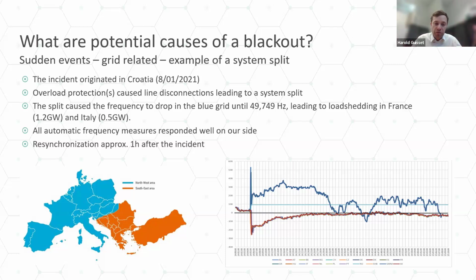When you go into over frequency, you have to stop production. So the different TSOs had defense plans in place, which lowered the production. But the blue area went into under frequency because there was not enough production and too much consumption. That is where the load shedding plans were activated and where load was disconnected in France and Italy, which restored the frequency. The two areas then had to reconnect. The balance in both areas had to be completely guaranteed before reconnection. And that took around 1 hour.